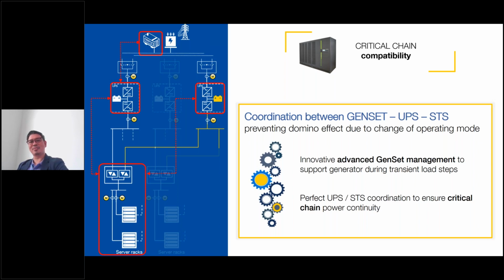On the upstream side, the UPS interacts with the genset, which everyone in the UPS market is familiar with. There's a function called ramp up—every time we transfer from utility to genset, we can ramp up the current going to the genset. The challenge is that load changes can still happen while the genset is running, so the UPS continuously monitors the genset's output to make sure it stays within certain conditions or ranges.